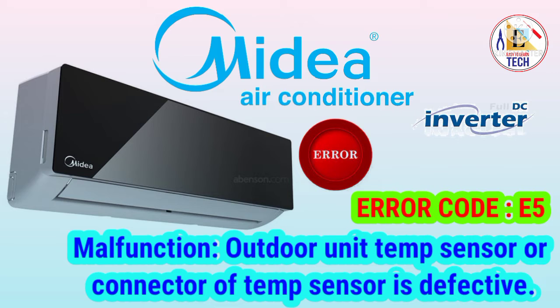The temperature sensor is installed just at the backside of our condenser unit. If the placement is not good, place it properly. Then you have to check the resistance of your temperature sensor, if the resistance is good or not. If the resistance is not good, it means our temperature sensor is faulty.